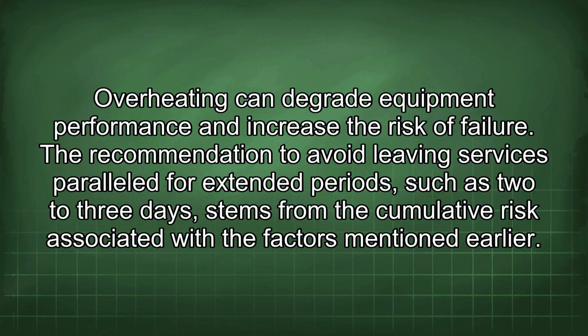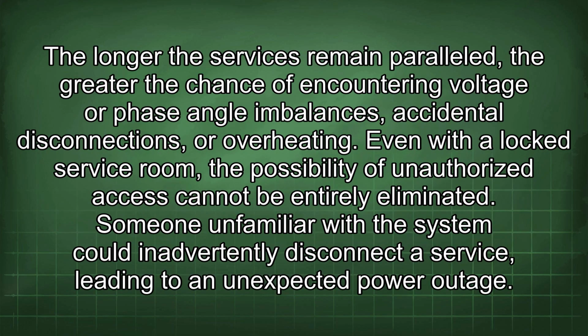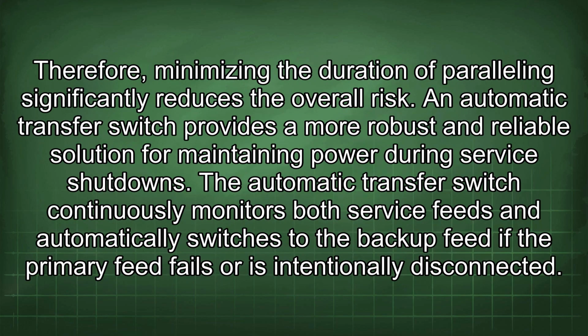The recommendation to avoid leaving services paralleled for extended periods, such as 2 to 3 days, stems from the cumulative risk associated with the factors mentioned earlier. The longer the services remain paralleled, the greater the chance of encountering voltage or phase angle imbalances, accidental disconnections, or overheating. Even with a locked service room, the possibility of unauthorized access cannot be entirely eliminated. Someone unfamiliar with the system could inadvertently disconnect a service, leading to an unexpected power outage. Therefore, minimizing the duration of paralleling significantly reduces the overall risk.